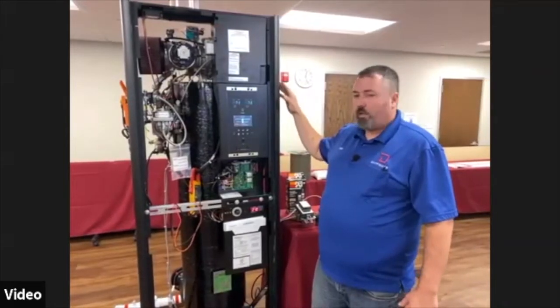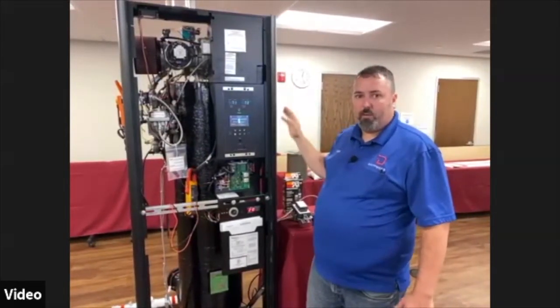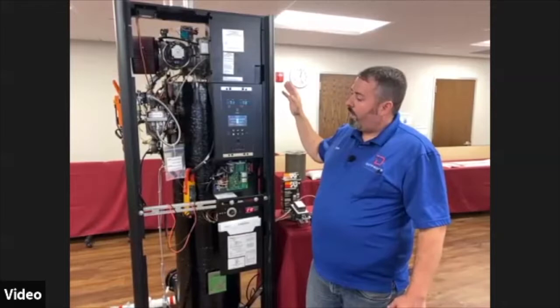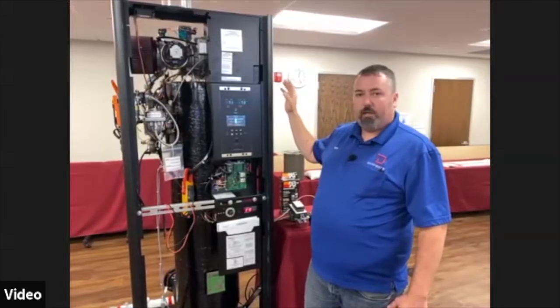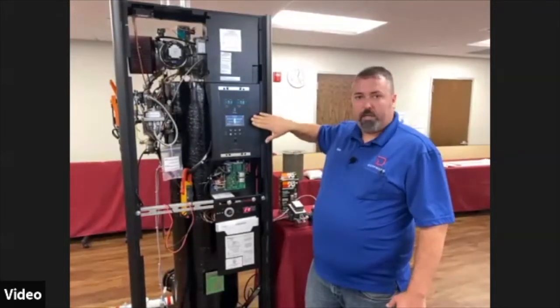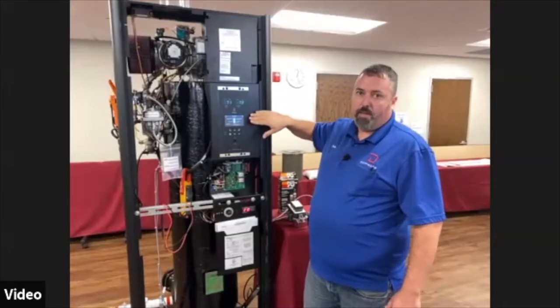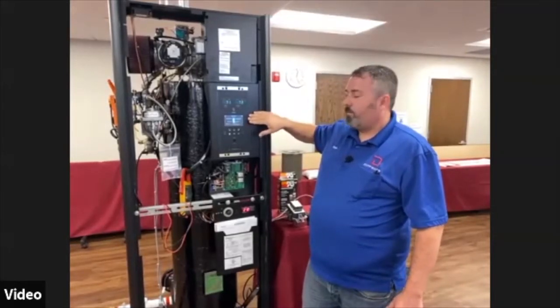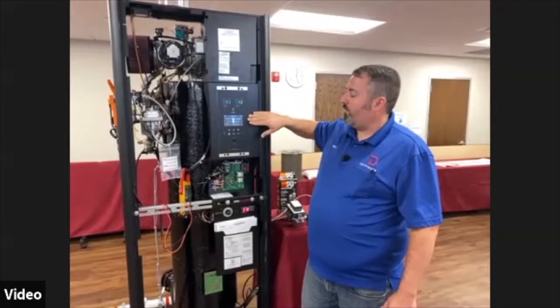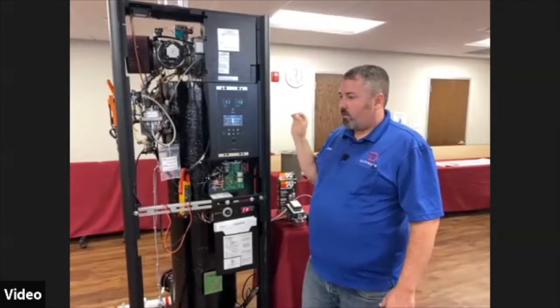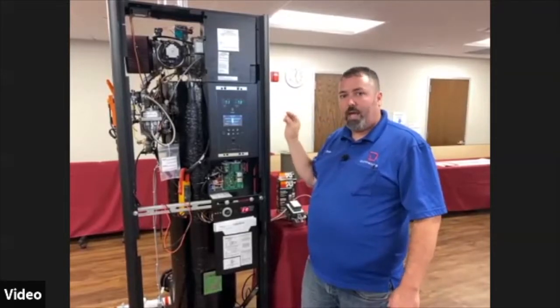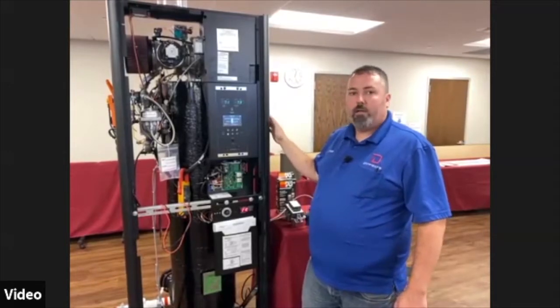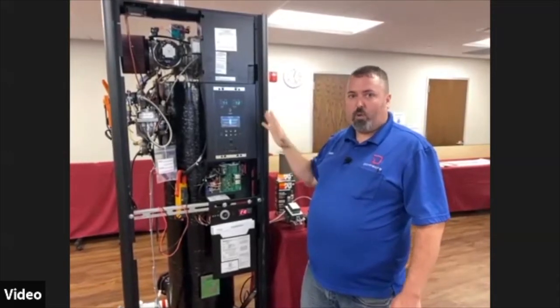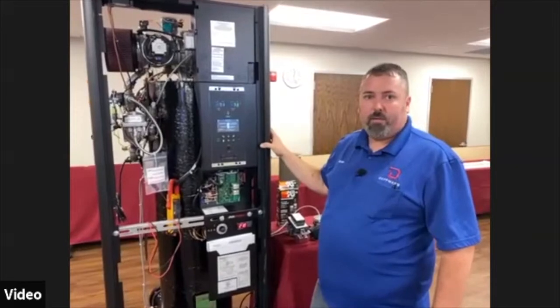The ignition trial starts with the blower dropping down to about 30% fire rate, and the igniter starts sparking. The screen will tell you cleaning igniter. That will last 7 seconds. That has two purposes. The first is it lets the spark get good and strong so that if you happen to be building a carbon bridge, the carbon bridge should blow apart and keep itself cleaned off.